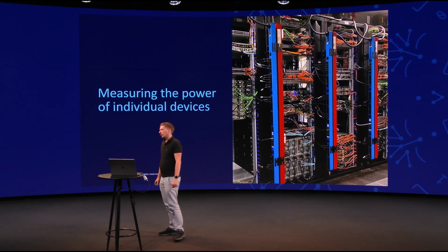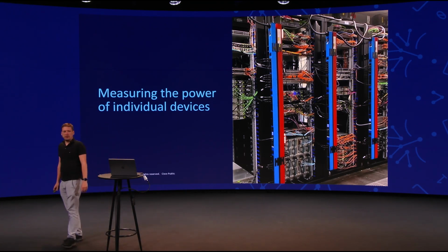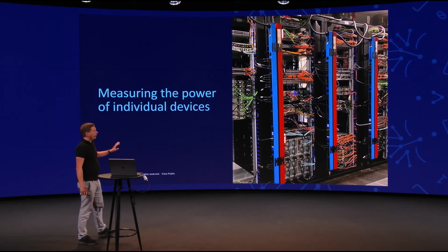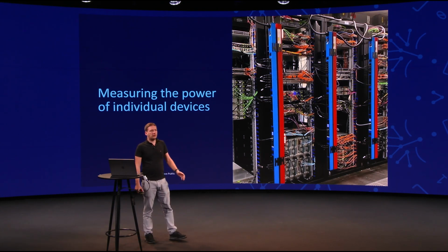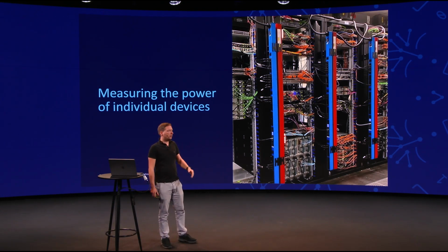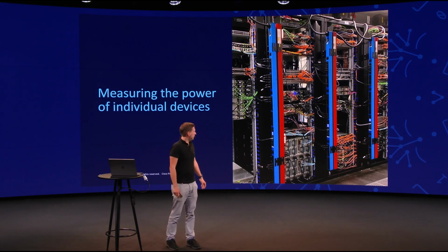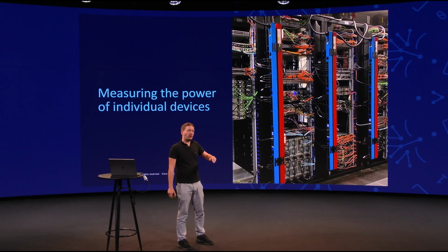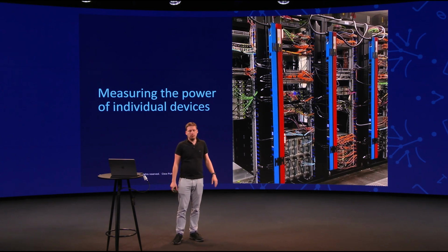Fortunately, there are lots of sensors, as you know, in our devices already, and some of these sensors actually measure power for us. It depends a bit on the kind of device what these sensors are. So if we assume our data center is fed with AC power and the devices are converting it to DC, then usually we have power sensors on the power supplies inside our devices that tell us how much DC power is going from the power supply into the various components of the device, right? So that's something that we can measure.